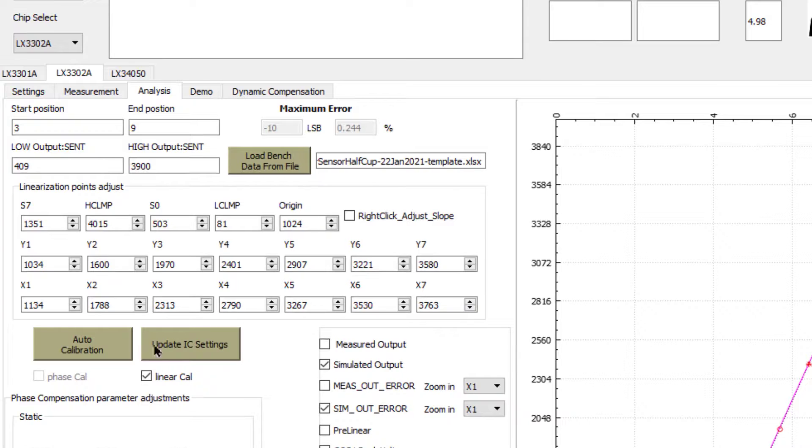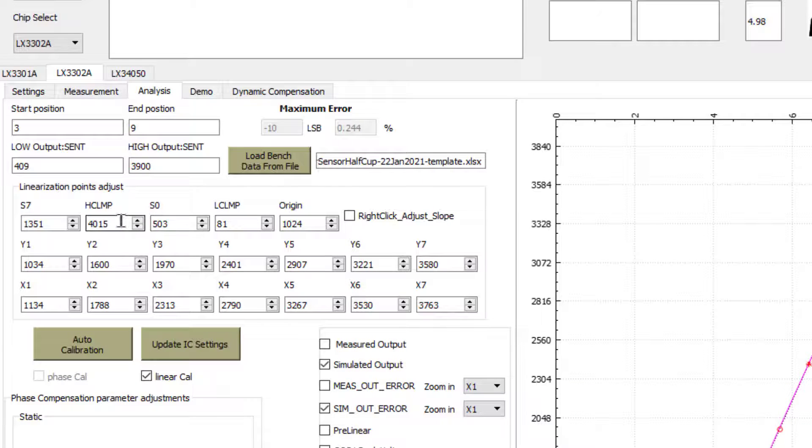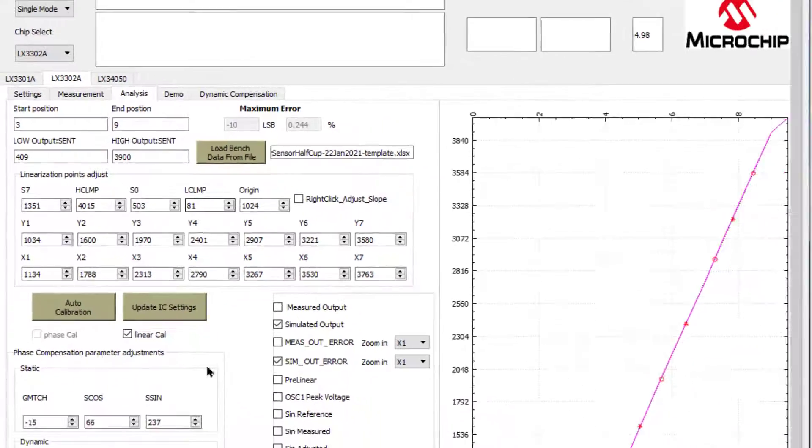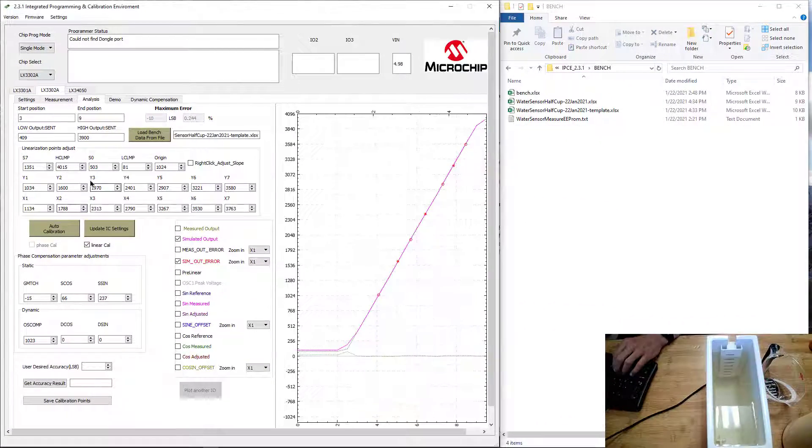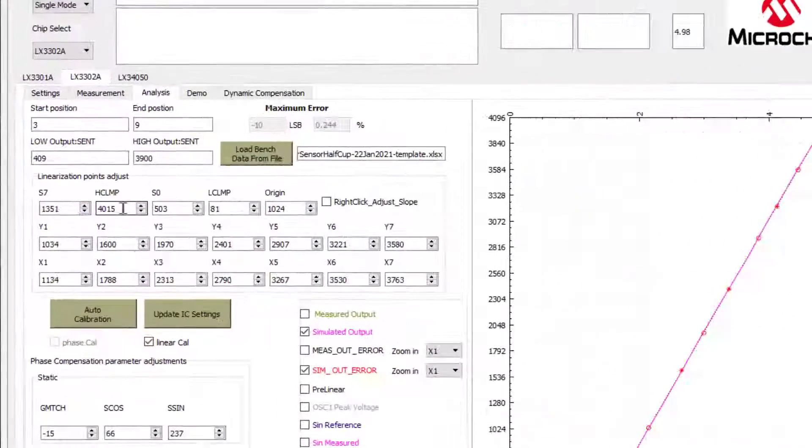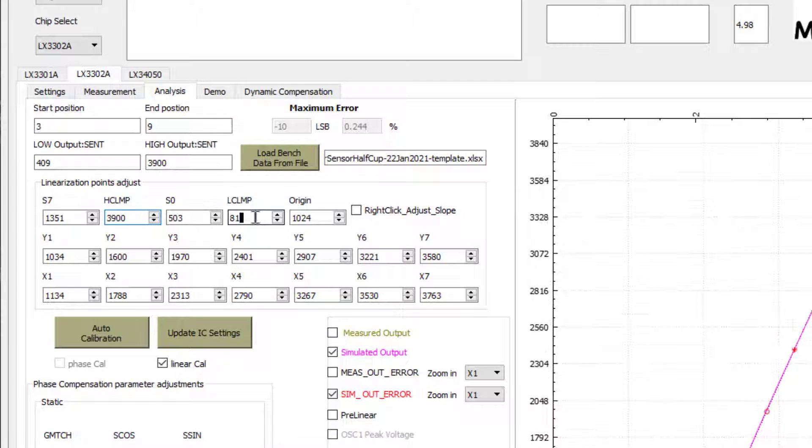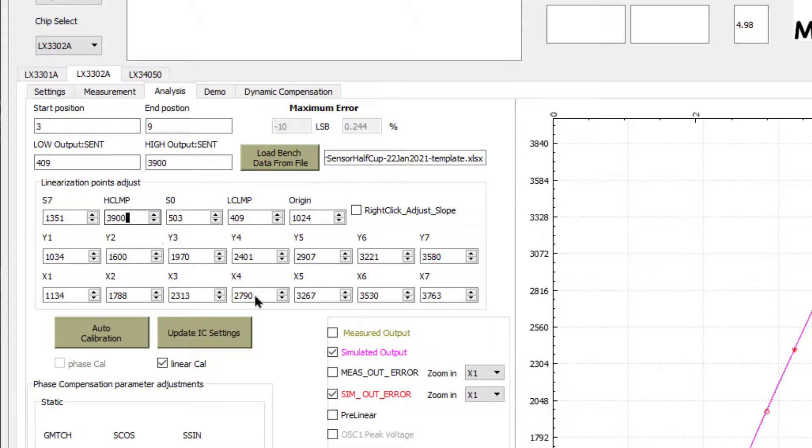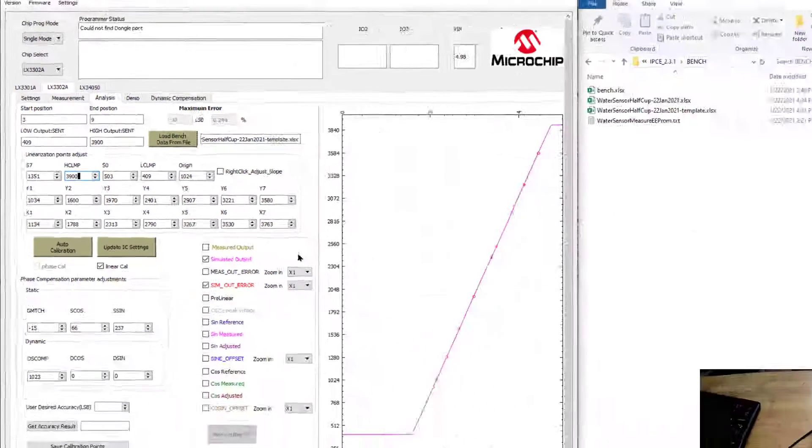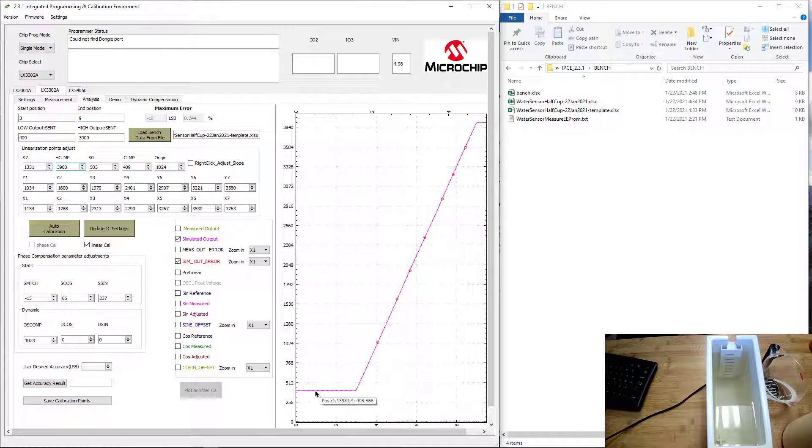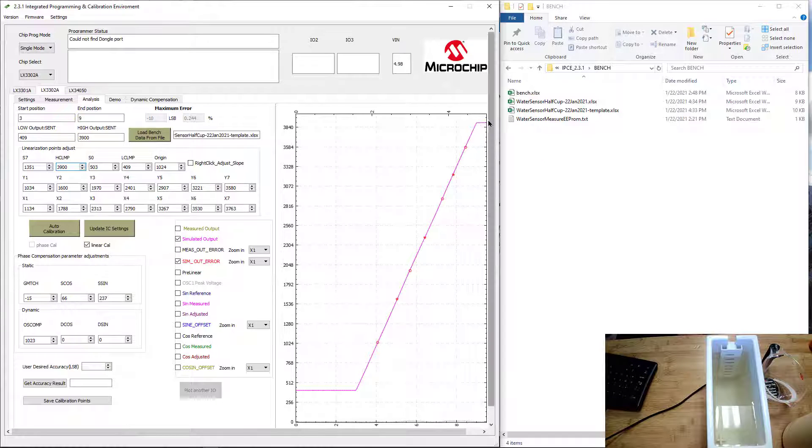After calibrating, we're going to set the H clamp and L clamp regions. H clamp, or high clamp, means anything above this value gets clamped. The low clamp means no signal below this value will go below the low clamp level. Above 3900, I'm going to put a clamp region, and below 409, I'm going to put another clamp region here. Now you can see that anything below this value will be clamped, and anything above the value is clamped there.